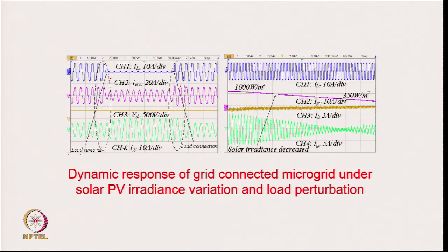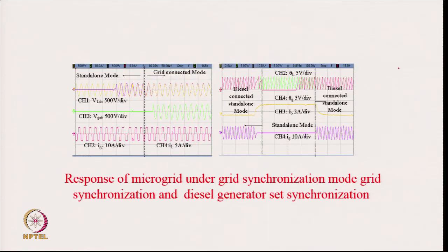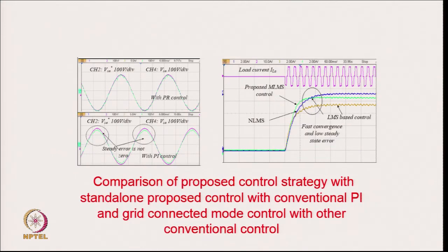Hardware of the developed prototype system is presented. Grid current and grid voltage are shown with load current. The grid current THD remains less than 5 percent and voltage THD also less than 5 percent even in distorted grid conditions. Load reduction dynamics show how the battery current changes and when solar generation is changing how the PV and battery current respond — battery gets charged more. Load balancing is demonstrated during load change. Islanding mode and synchronization back to the grid are shown, as well as DG set operation — making the DG set off and then reconnecting to the DG set with synchronization.